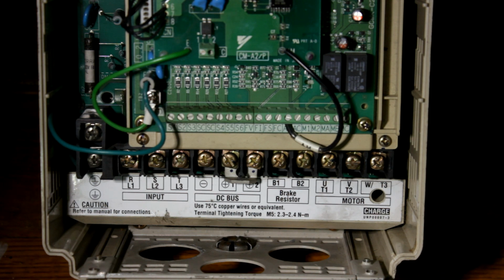Other older types that aren't like this, you would see a couple of different inputs. You'd see the input on the left side, but then there would be another input that would say control power input or control power, something of that nature. Those types actually do have separate power supplies and separate transformers for their control boards and control circuits. Like I said, most newer variable frequency drives that are low voltage, from 0 up to 1000 volts, are powered directly from the DC bus.